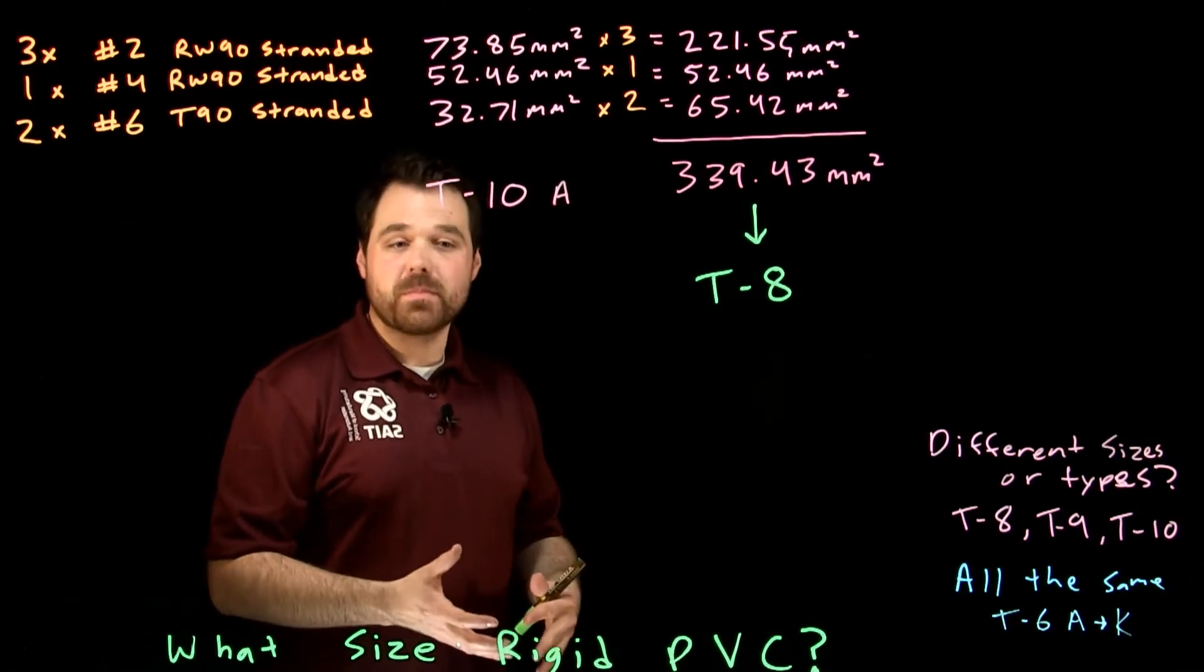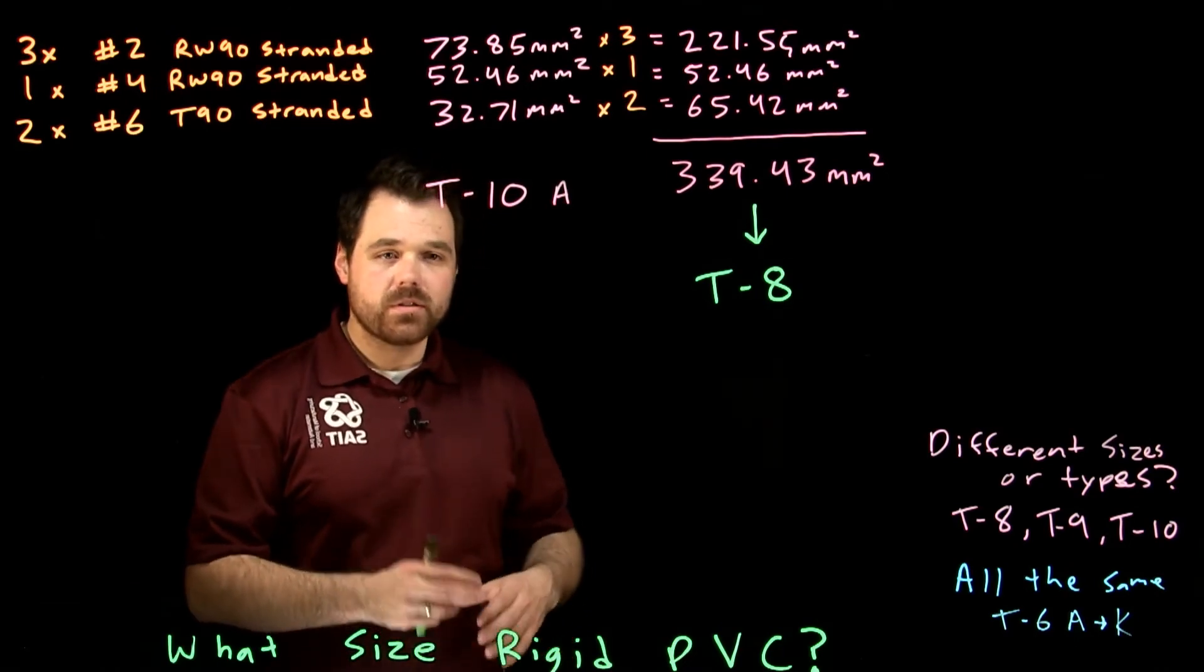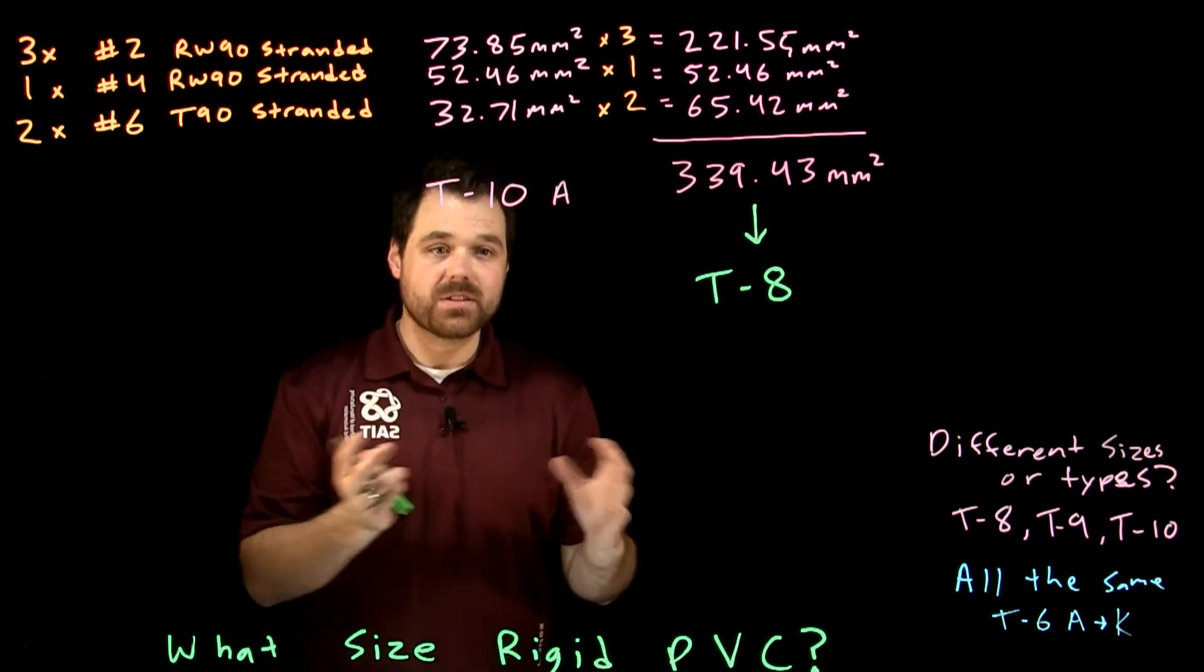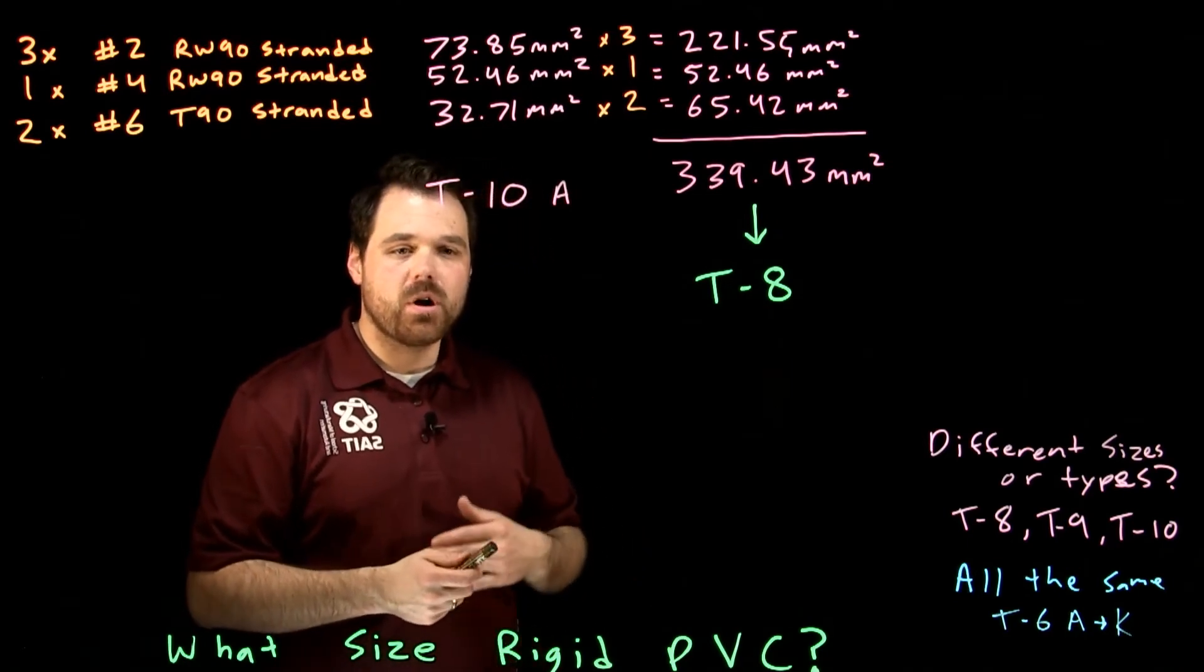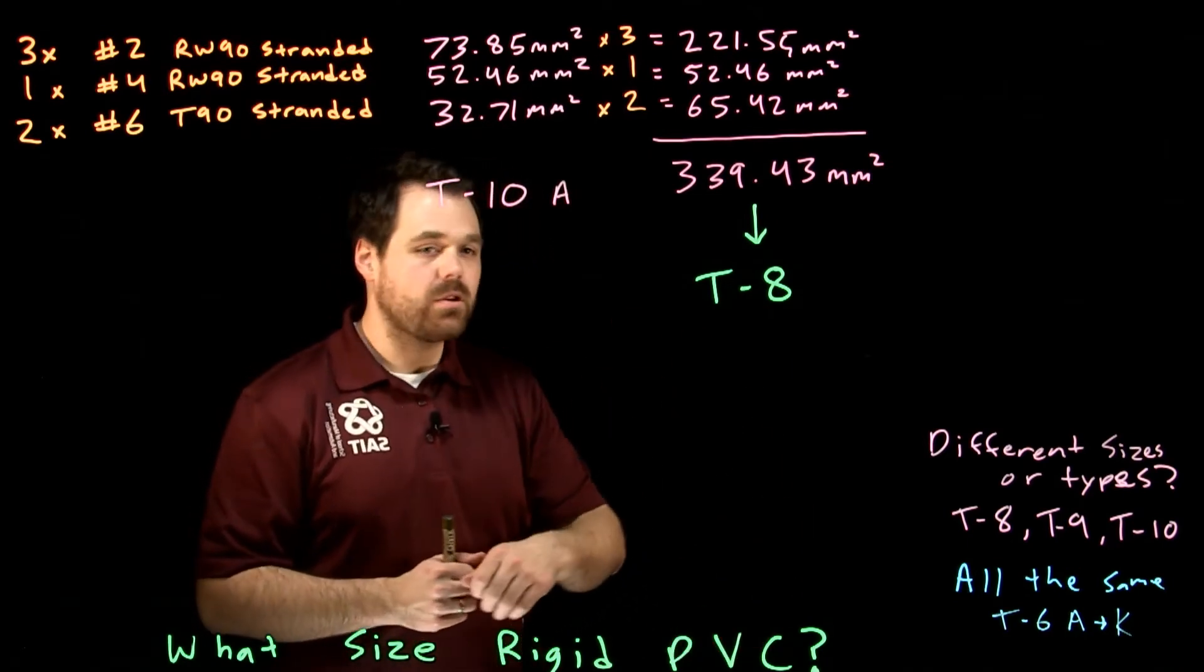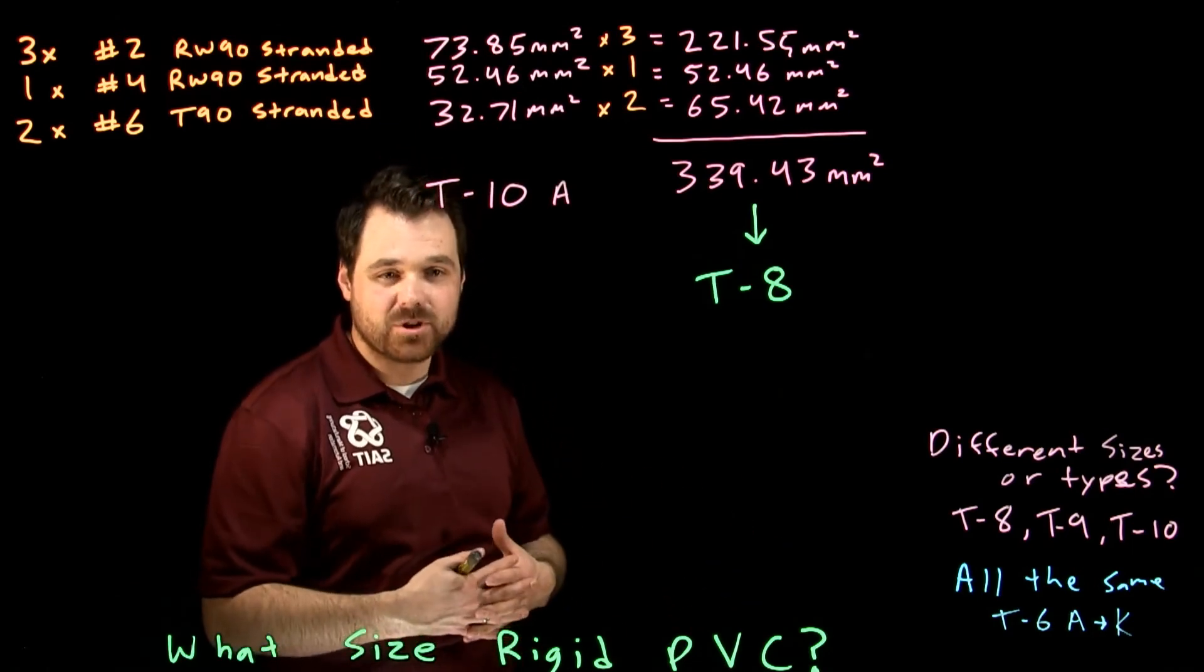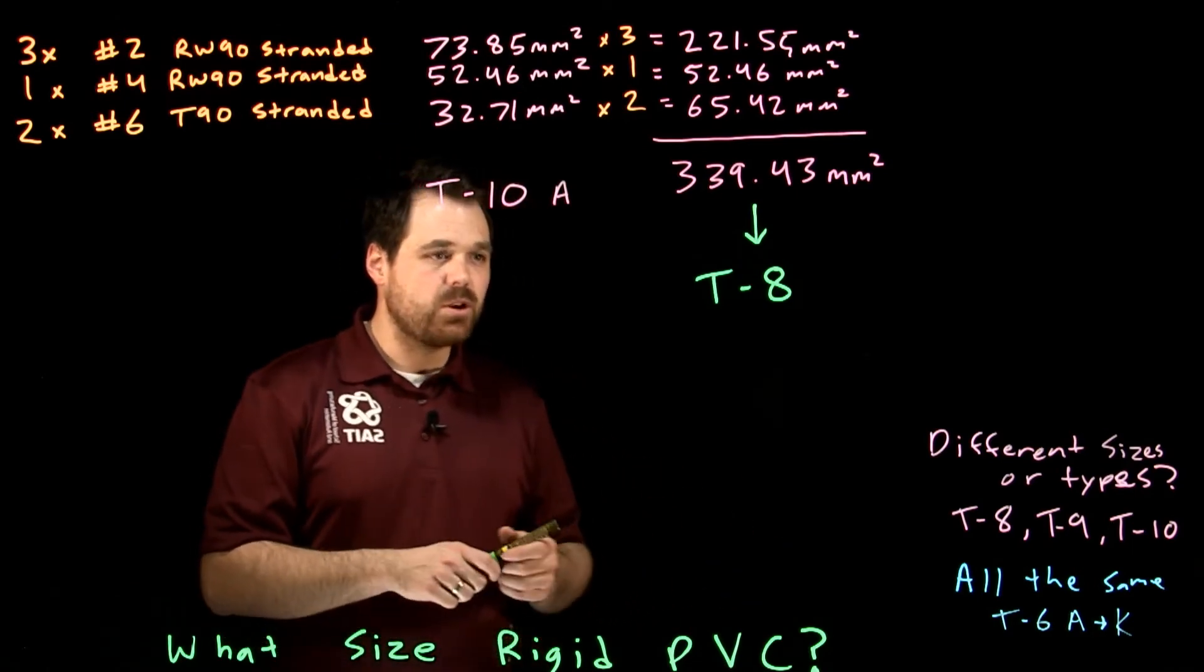The reason we're only allowed to take up forty percent of the conduit is, remember, these are a bunch of circles together inside the conduit. There's going to be little gaps in between them. Also we want it to be safe when you are pulling the conductors through the conduit or if you need to remove a conductor. We need space so we're not causing damage to these conductors.